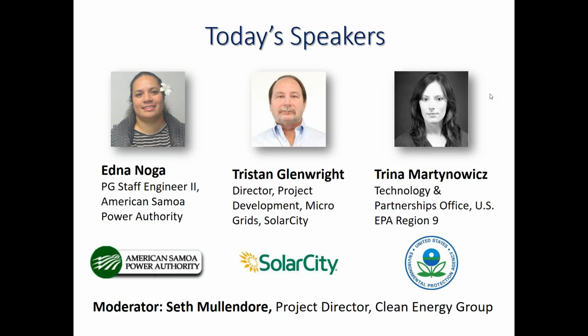Sure, I'll start with the frequency. The battery system and the power electronics integrated with it are the primary frequency and voltage source on the island when the diesels are off, which is most of the time. In terms of reliability, this is a very highly reliable energy storage system, and we're seeing that in the numbers. After several months of service, we're seeing very high reliability, and there are redundancies built into the system. For example, the PV system uses string inverters, so at any time if we lose one or two, out of a total of 44, it's not a significant impact to total production.